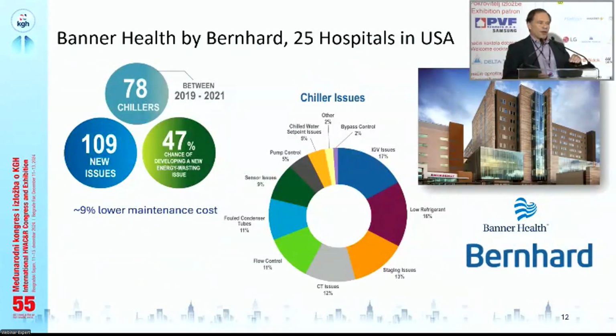And the interesting thing here is that there are many different things. The chillers are in the middle of a lot of systems, and you need to have all these working well, including the internal controls of the chiller, the BMS controls, and all the supply systems on the outside to have a good system. But most systems, somebody said before, you push the button and you leave them, and then everybody's saying it's not my fault, it's somebody else's fault. So you need to monitor, you need to make sure that it works well. And the conclusion of this project, when they had implemented it on all these 25 hospitals, was that they reduced the maintenance costs drastically.